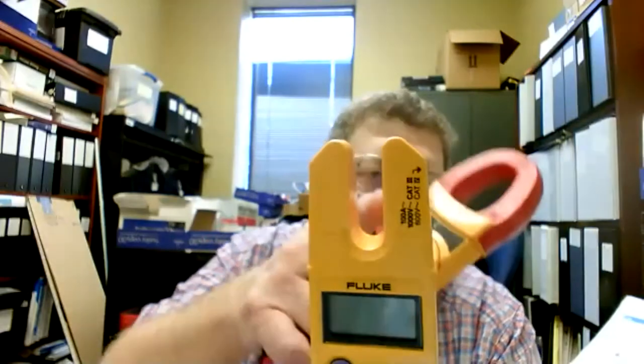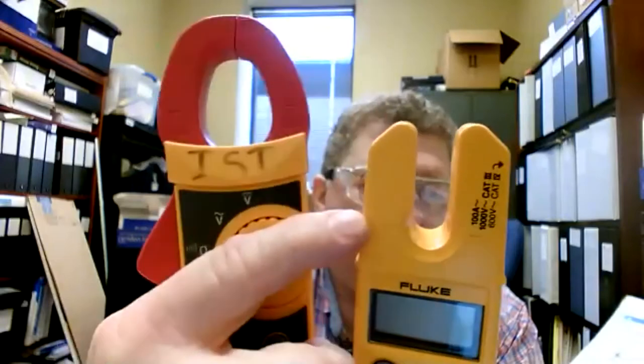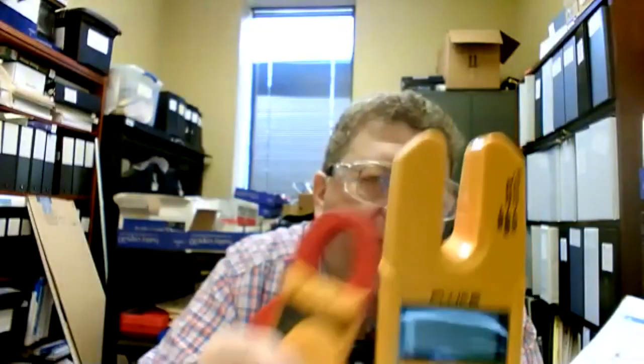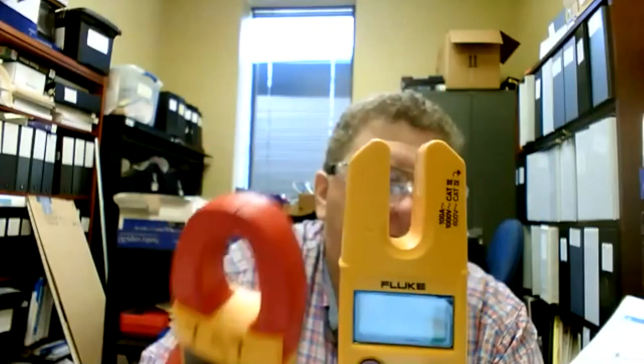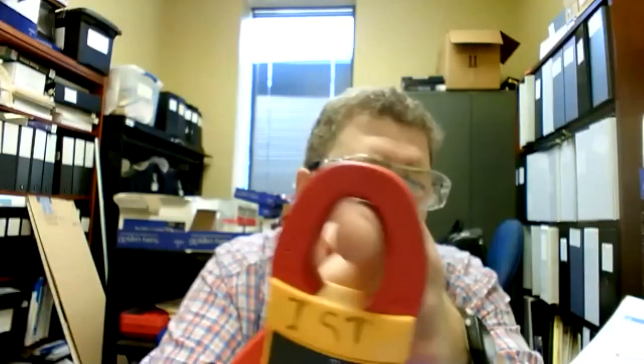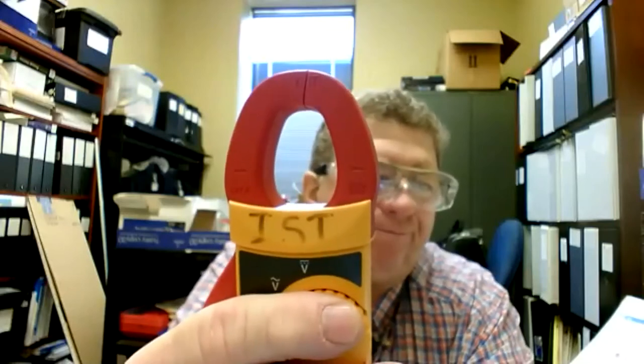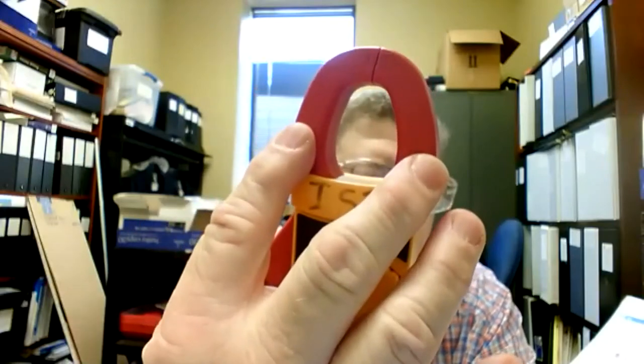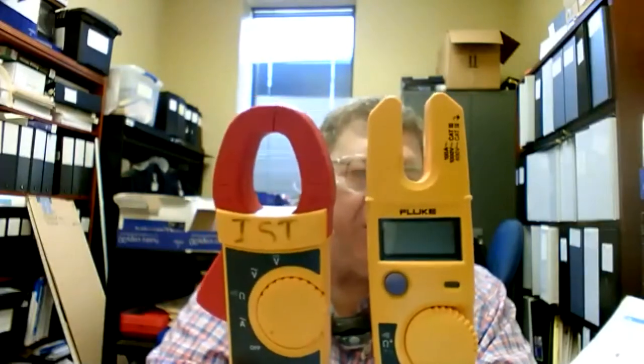Yeah. So the current can be measured. These newer current meters or ammeters have an open fork on them. You'd have to get the wire down in this area where the lines are in the sensing range to get an accurate reading. If your wire's up in here, it's not going to be a guaranteed accurate reading. But on this type, it has an open jaw. So you put the wire inside the jaw, and it doesn't matter where it is in there. It's more forgiving than an open fork is. So either one can measure amps.